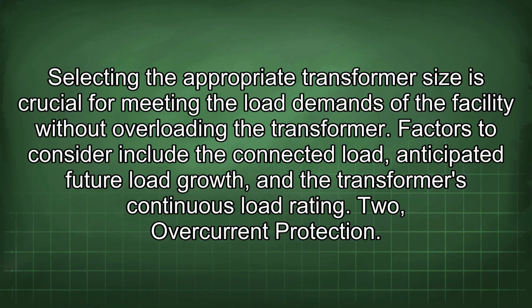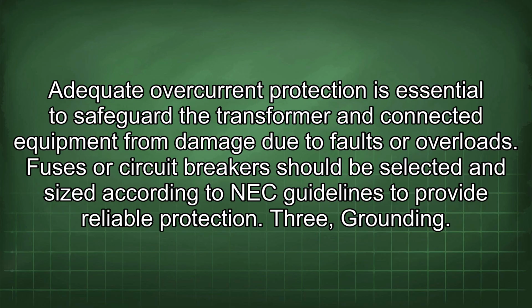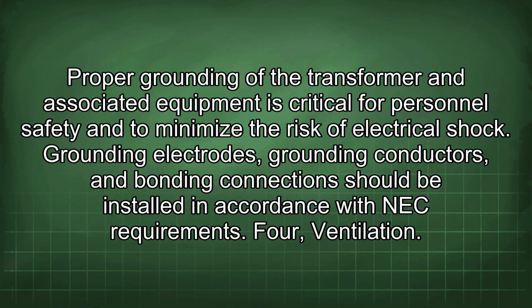2. Overcurrent protection. Adequate overcurrent protection is essential to safeguard the transformer and connected equipment from damage due to faults or overloads. Fuses or circuit breakers should be selected and sized according to NEC guidelines to provide reliable protection. 3. Grounding. Proper grounding of the transformer and associated equipment is critical for personnel safety and to minimize the risk of electrical shock. Grounding electrodes, grounding conductors, and bonding connections should be installed in accordance with NEC requirements.